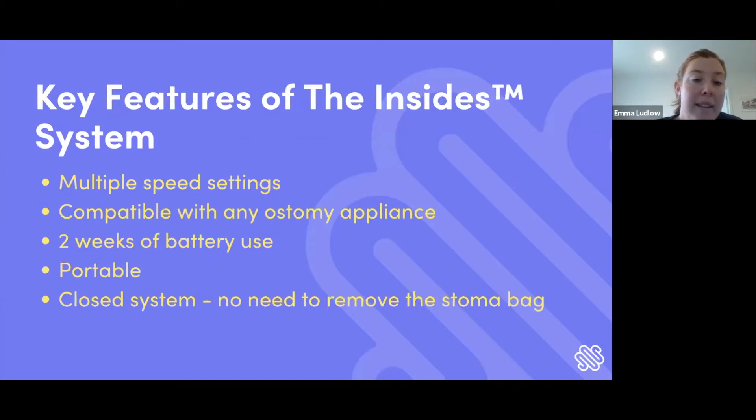The key features of the Insides system: there are multiple settings and no set flow rate on the driver — it deals with whatever viscosity of chyme is in the bag. The Insides tube is compatible with any ostomy appliance, and the tube length is customizable, able to be cut to whatever length is needed. The Insides driver has two weeks of battery life and we provide a power pack to recharge; a recharge takes about four hours. The driver is portable, does not need to be attached to the stoma bag, and weighs around 500 grams, so you can leave it on the bedside and use it when applicable. It's a closed system, so there's no need to remove the stoma bag and no messy hands.